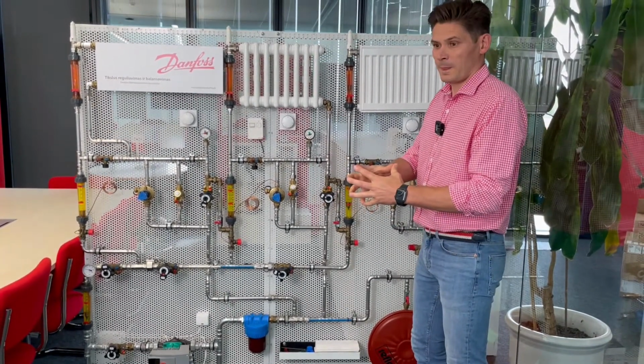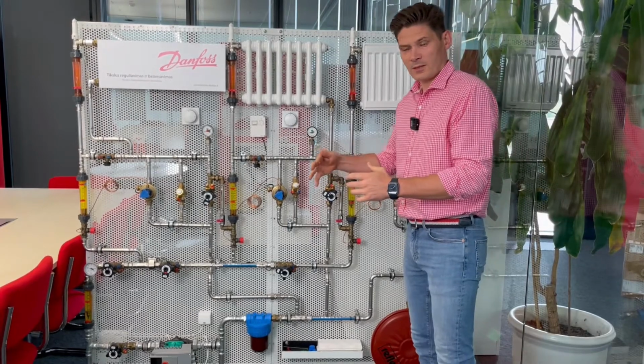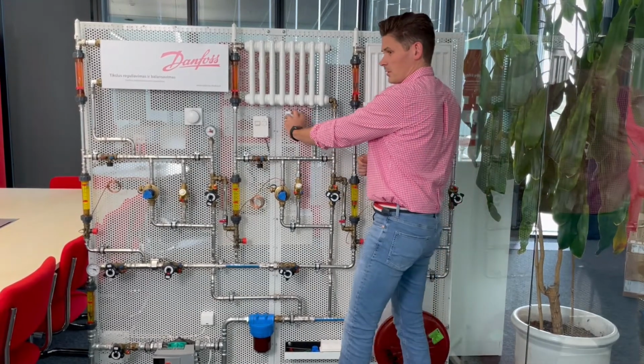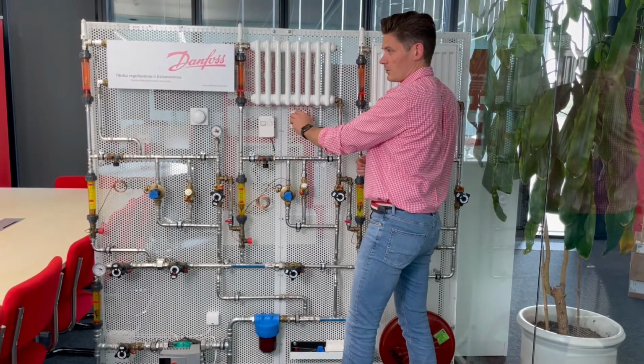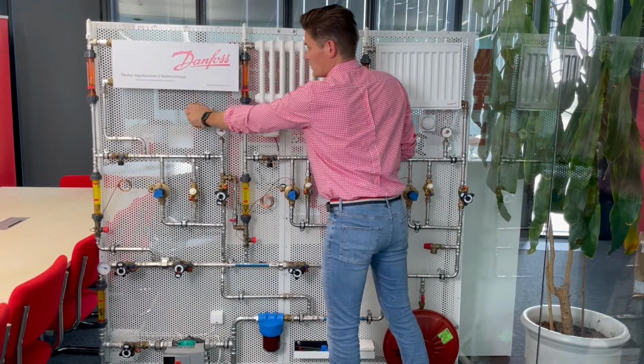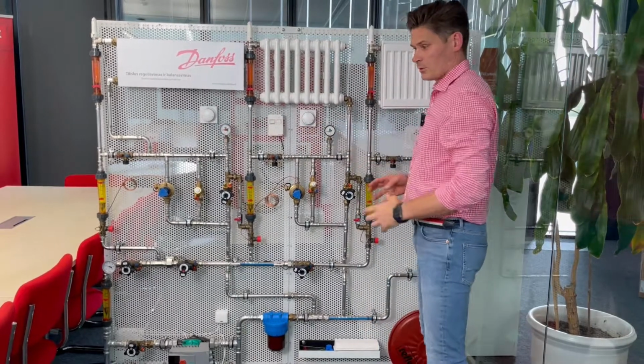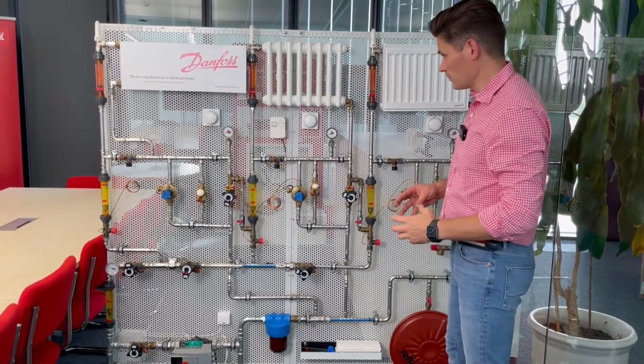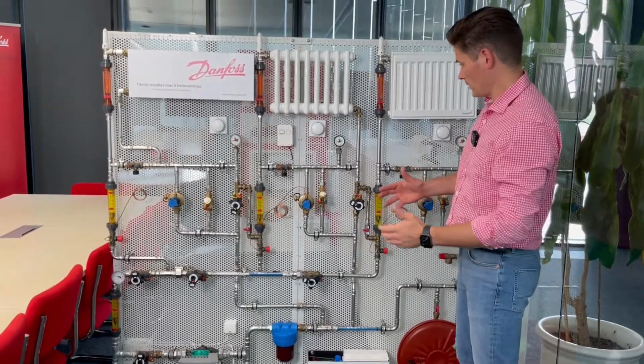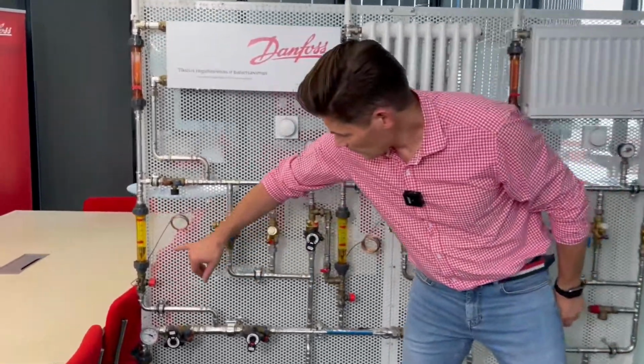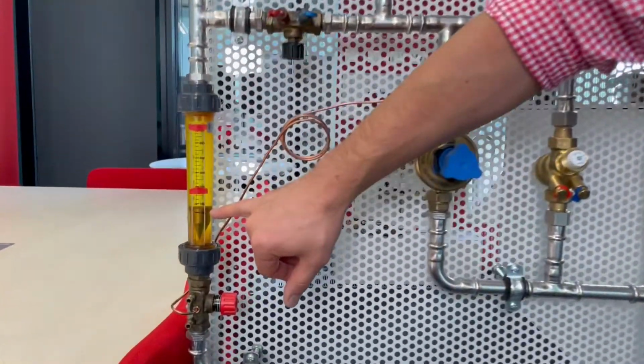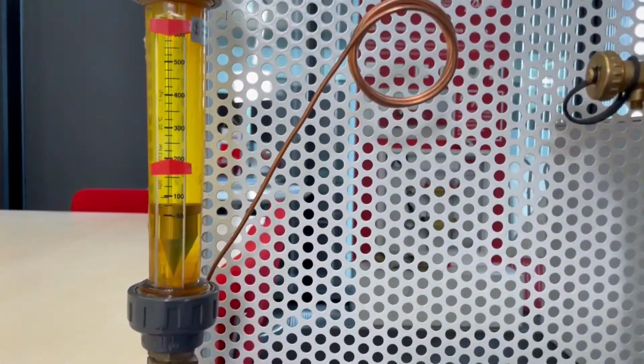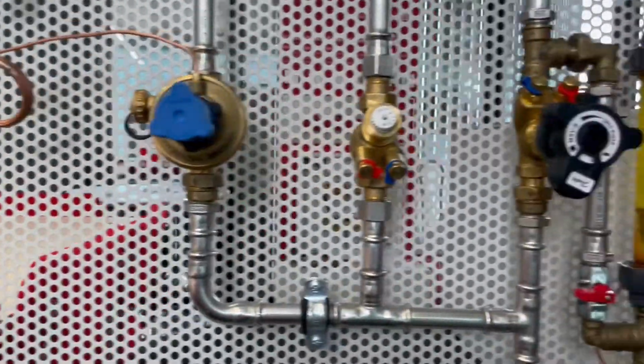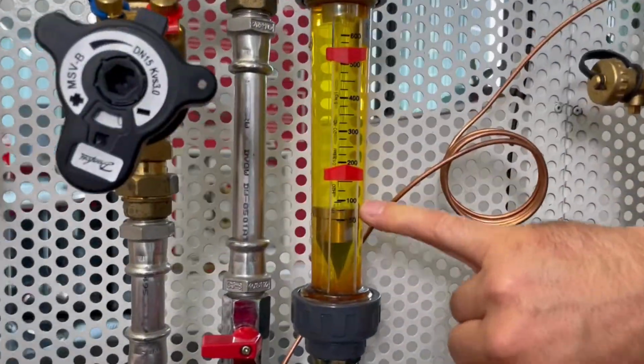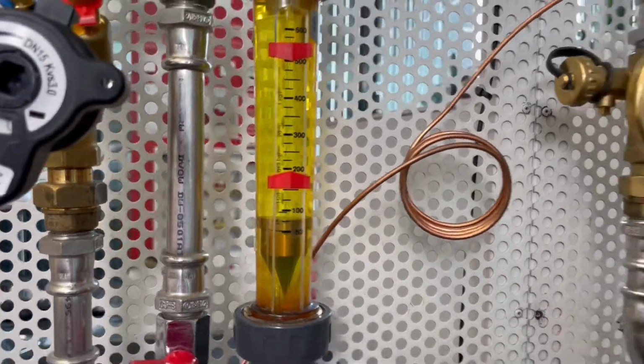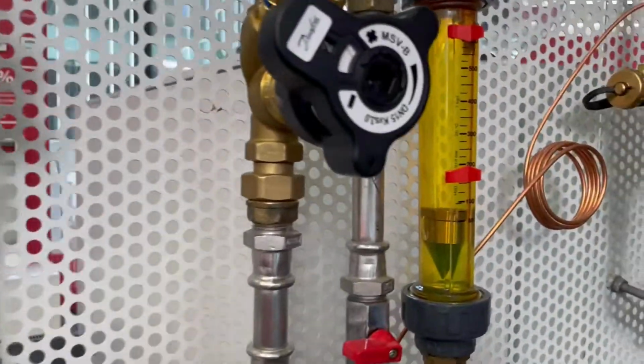During night time, we have colder weather outside, so all house thermostats are opening. Again, we need the full capacity of our heating system. And now take a look at what we have in our system. First riser, it was 200 liters. Now we have something like 70 liters. Here we had 200. Now we have 70 liters. And the last one also 70 liters.